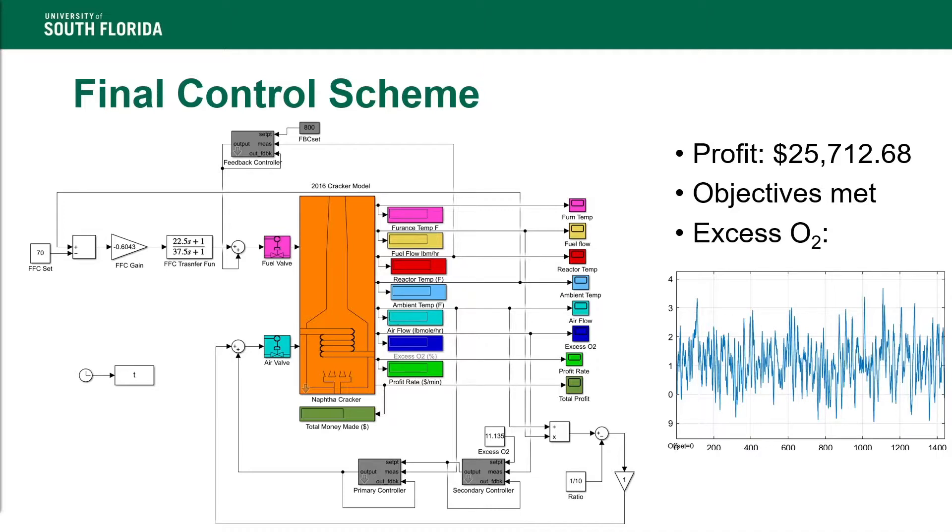The set point of the excess O2 had to be raised to 11.135%, which lowered the profit. The tradeoff here was between the profit and the excess O2, but to ensure safe operation of the plant, the loss in profit was seen as acceptable.